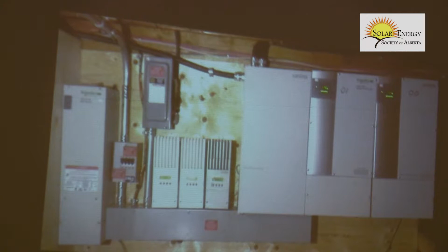This is Schneider Electric's XW system, and it has a comm box on it. So I'm actually able to log in remotely to this system, and I can adjust settings on the automatic gen start, on all the charge controllers and the inverters, and that type of thing. I can monitor the system and see how it's performing remotely, because they have satellite internet to the lodge, so I'm able to log in remotely through their router.